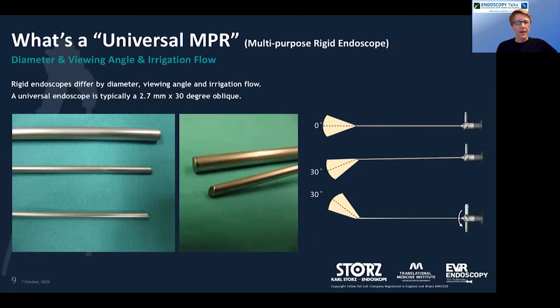The 0° is basically allowing you to see the field of view, but only directly what's in front of you. So that can be useful if you're first starting out, for instance, with laparoscopy. It gives you a true image of what's directly in front of you, so it's quite intuitive for the beginner. But when you're working in tighter spaces, it's got some significant limitations.